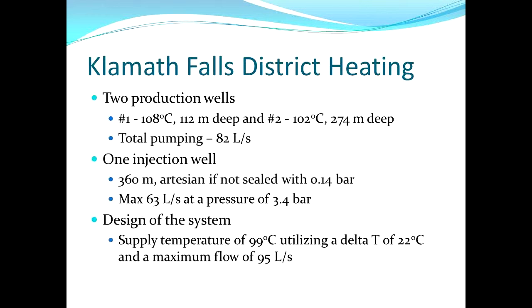They utilize a 22 degree C delta T that they take out. Everybody on that system gets that supply temperature, or 1 degree less, because by the time it gets to the greenhouse it might have lost some heat. But everybody gets that temperature and they're expected to take out 20 degrees C. If you take out more, they don't care.